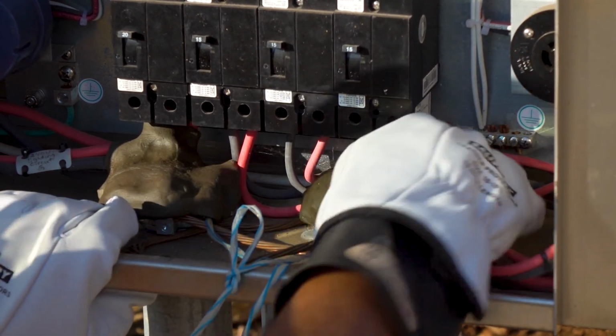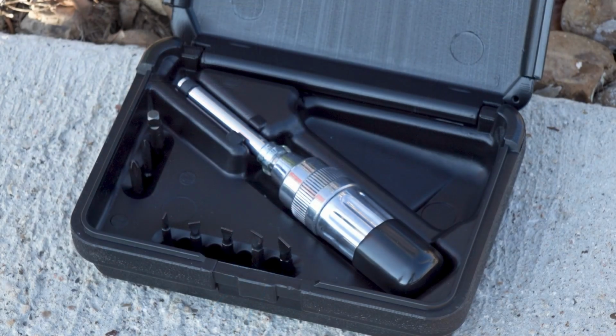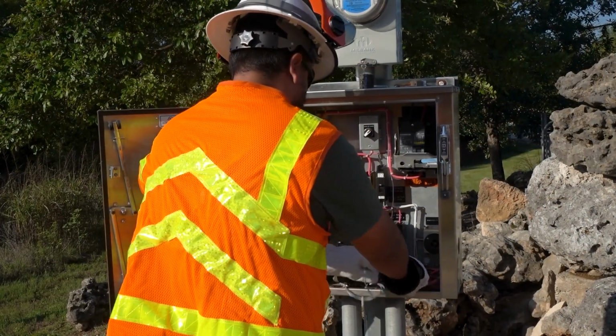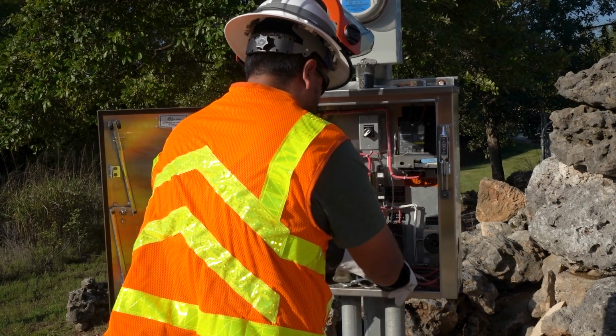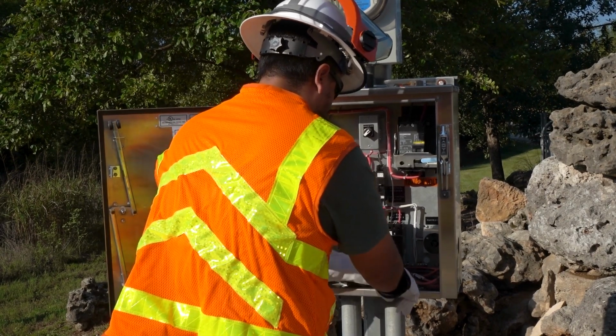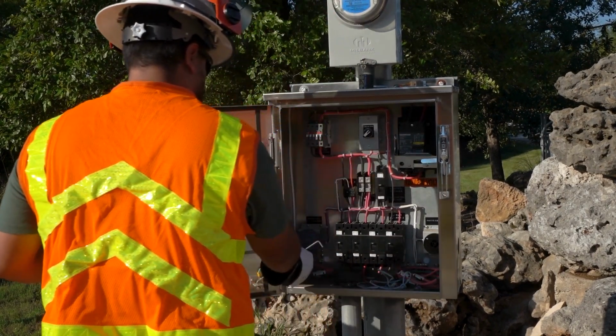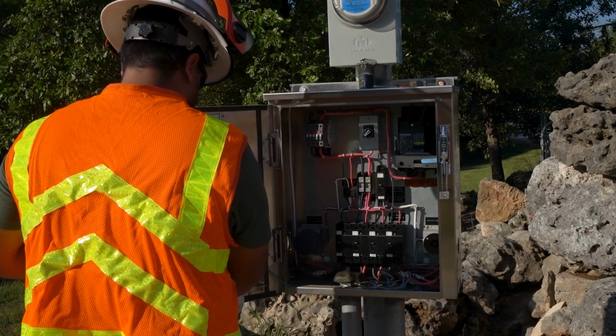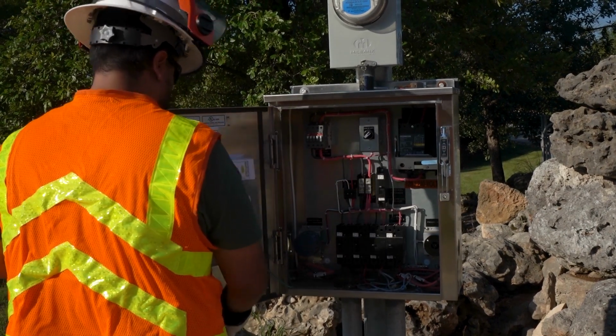The inspector will also have the contractor confirm the correct torque has been applied to each of the conductors connected to the load side of the branch circuit breakers. These connections are made in the field by the contractor. Having completed the inspection of the service wiring, the inspector will then inspect the branch circuit conduits, conductors, ground boxes, and the other electrical equipment installed on the job.